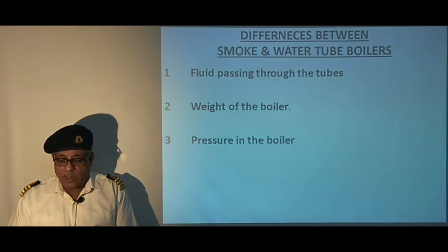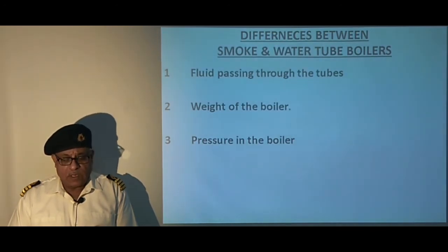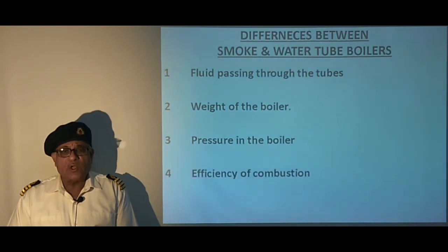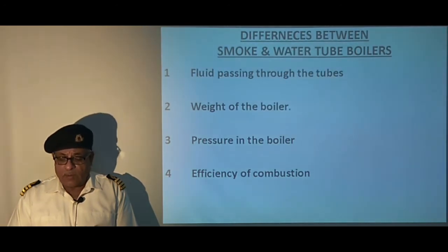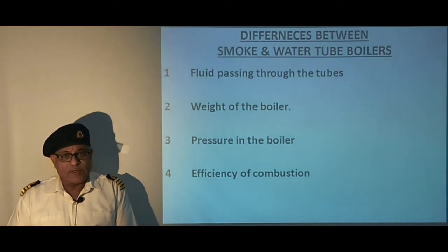Third, on the basis of pressure: smoke tube boilers are used for low and medium pressures and have low efficiency, whereas water tube boilers are used for medium and high pressure and have higher plant efficiency. Regarding efficiency of combustion, smoke tube boilers have less efficient combustion due to the restricted size of the furnace surrounded by water, as a large furnace would require more wall thickness, reducing heat transfer. Combustion in the water tube boiler is more efficient and there is no restriction on the size of the furnace.